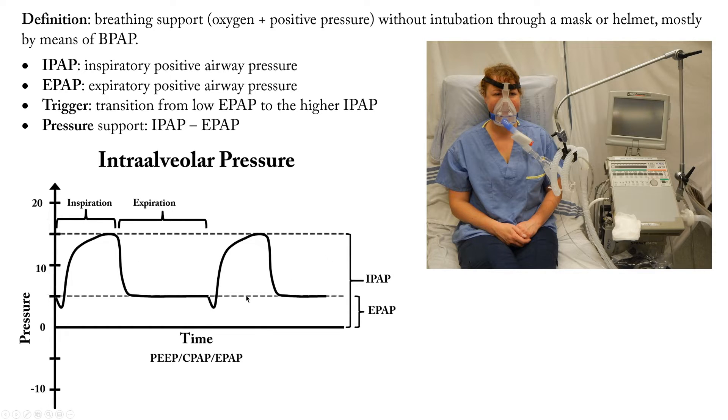This is the graph of the pressure-time in non-invasive ventilation. As you can see, there is a negative deflection — the patient started the trigger, and then the machine gave the positive pressure support.